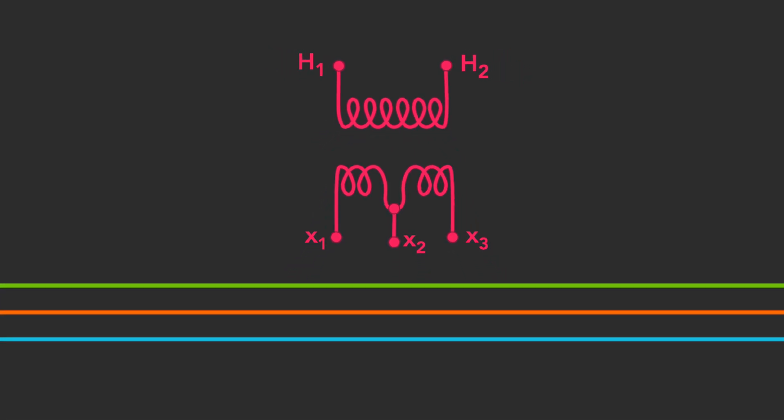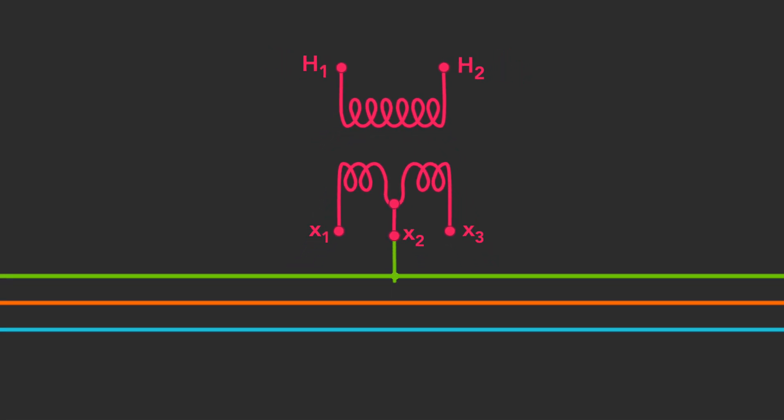It will consist of three wires. One wire, usually referred to as the neutral, is connected to the ground and the X2 bushing. The remaining wires, generally called hot legs, are connected through leads to the X1 and X3 bushings.